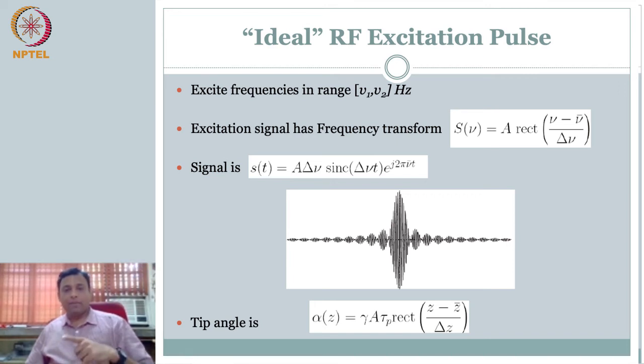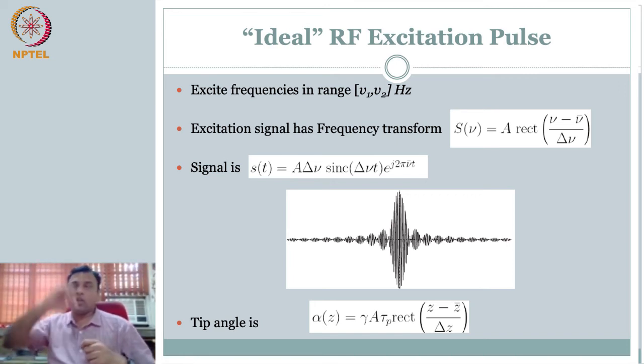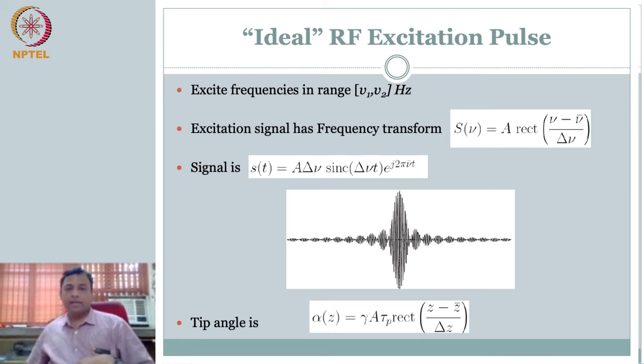So now another parameter of interest for your RF excitation is how long I apply this RF excitation. That will dictate my tip angle, which is related to the gamma, and your applied excitation pulse characteristic, tau. Okay, so let's jump in and see.